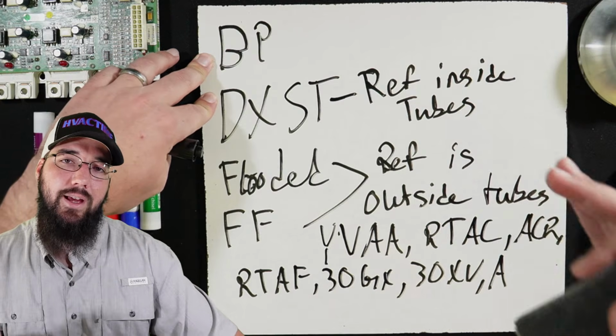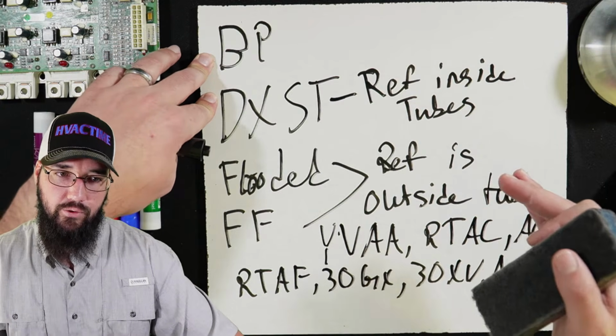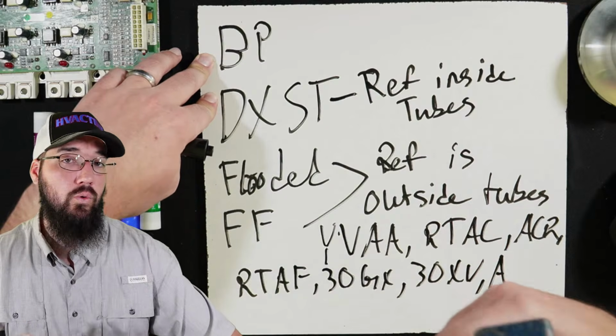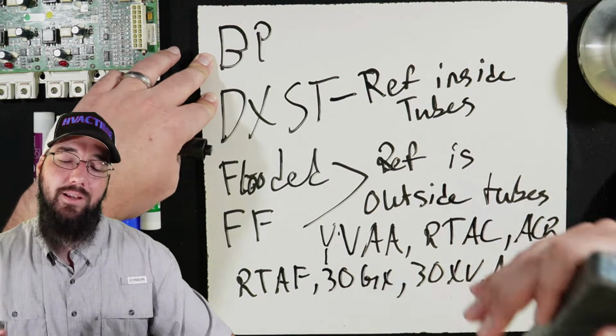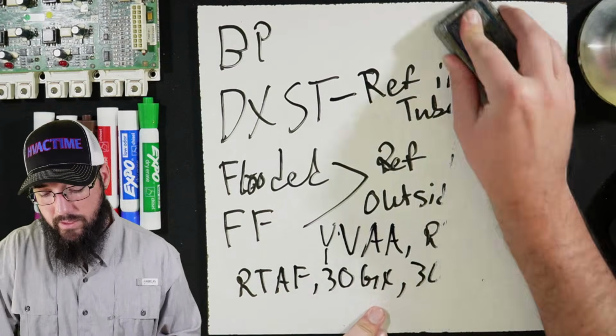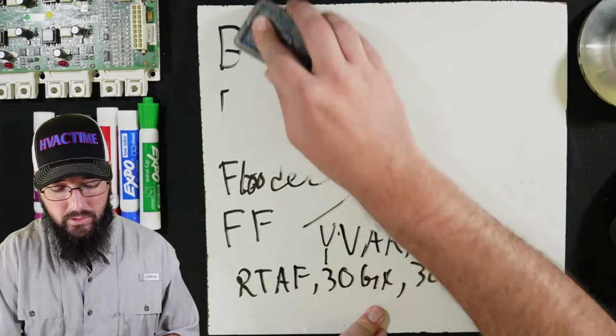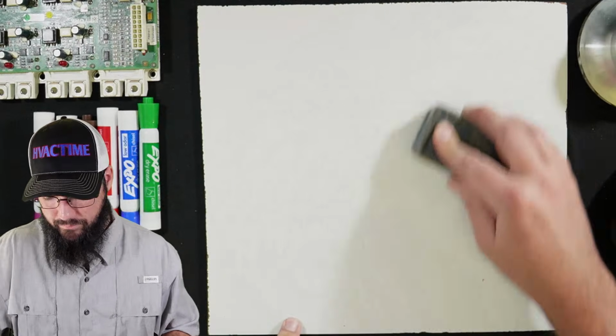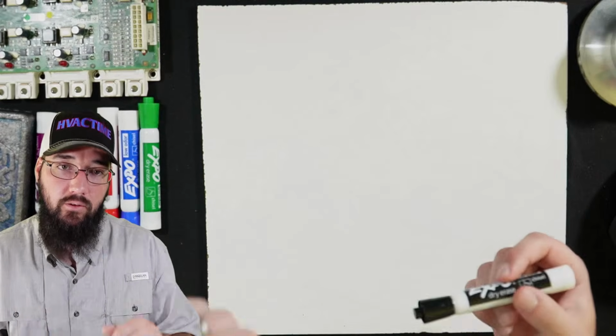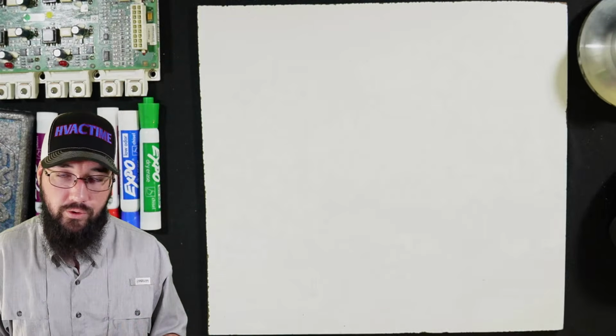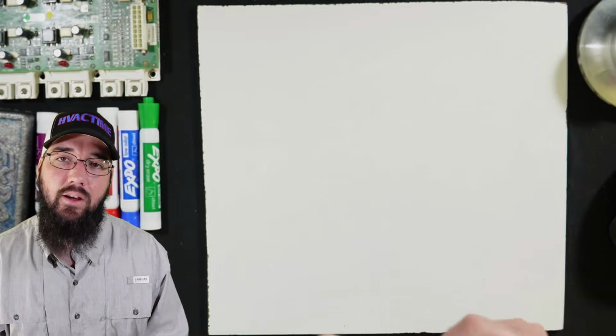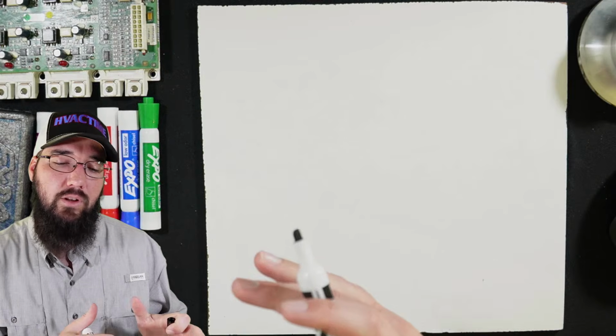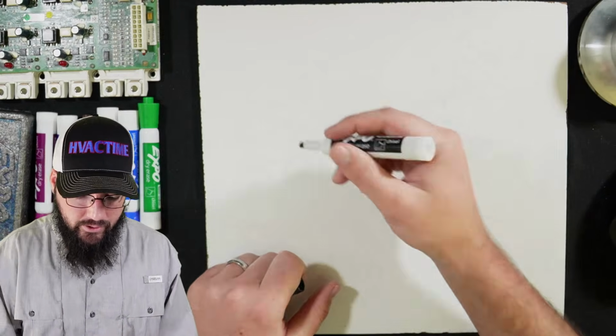What that means is that it is not worth the time or effort to try to do a push-pull or a pull-pull on those systems, because even if they do a pump down, the liquid refrigerant is not in a place where it is truly consolidated and easy to recover from. Just purely getting that liquid refrigerant out. And you still end up having a lot of liquid that has to be boiled out. And I'll give some examples of this.